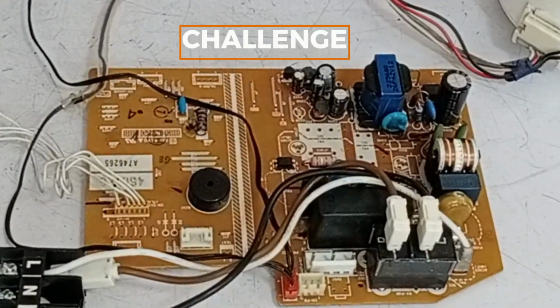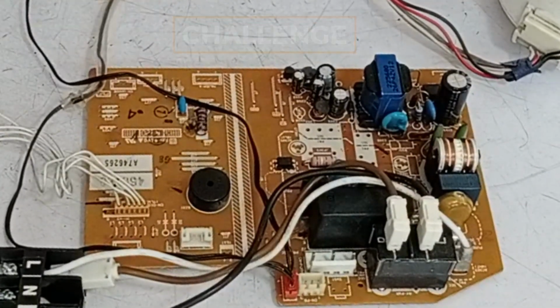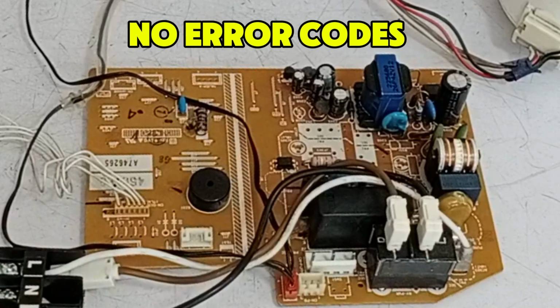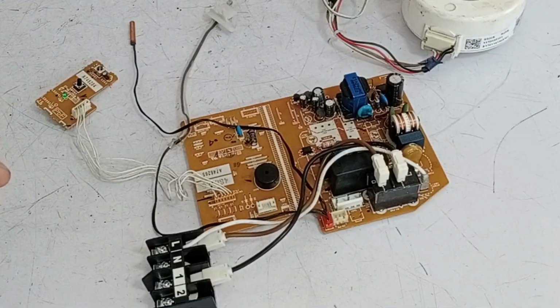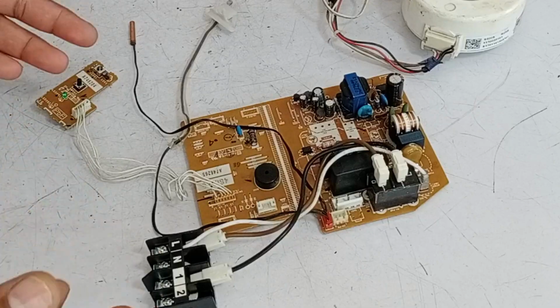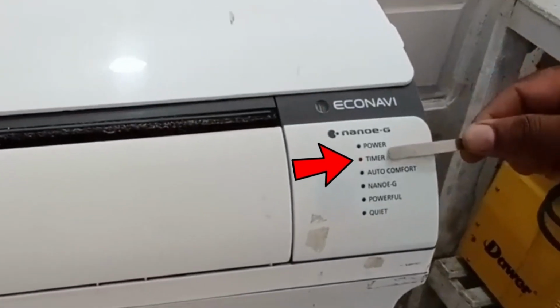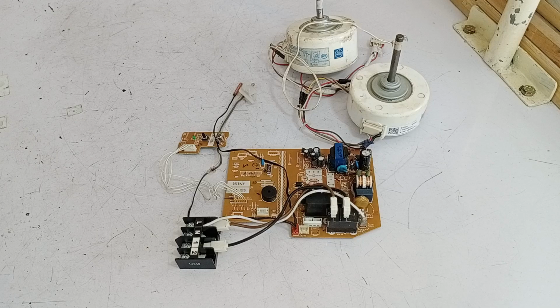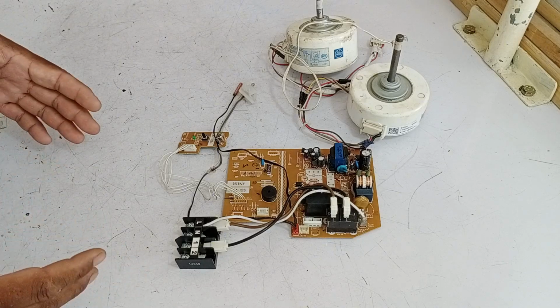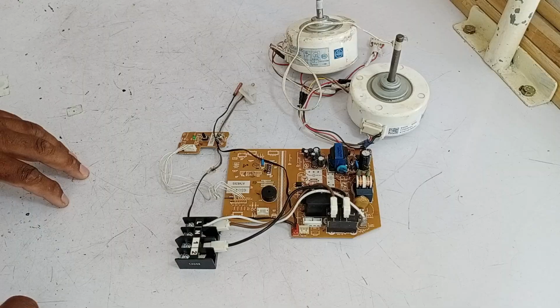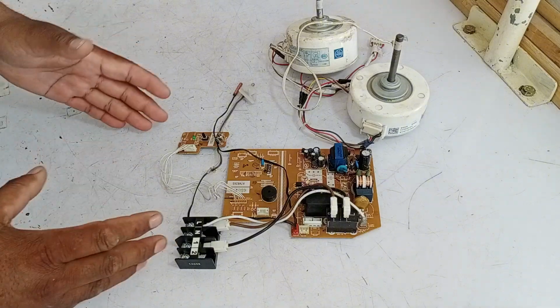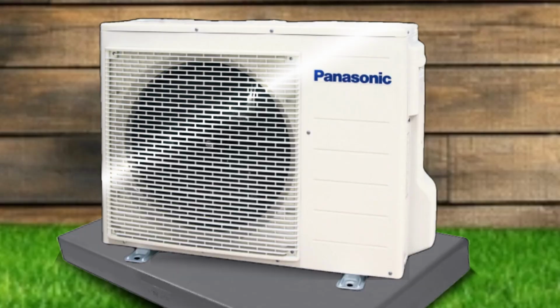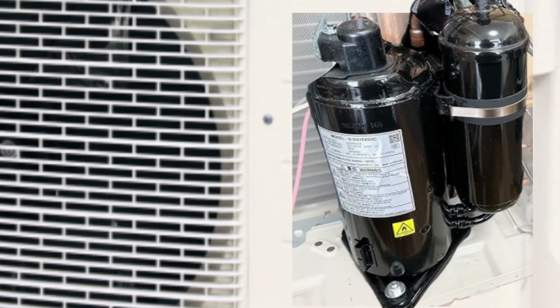Now, one challenge with this PCB is that it doesn't have error codes, which Panasonic often omits in these models. So, when a problem arises, you won't have error codes to guide you, making it harder to understand the issue. Now, I'll explain a few methods to help you check where the fault might be in the unit. When there's a tripping issue, it's not always just a problem with the PCB. The outdoor unit might also have its own faults that contribute to the issue.